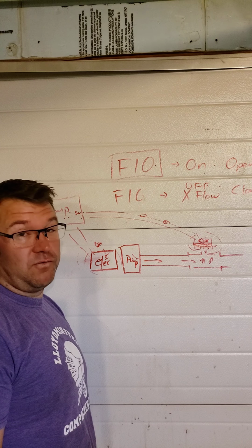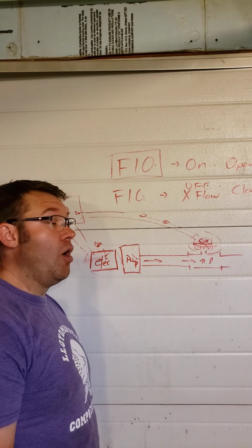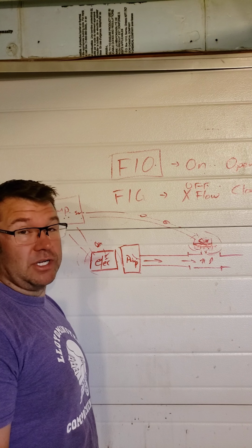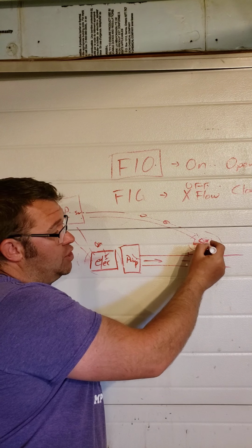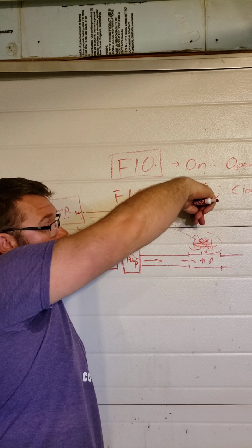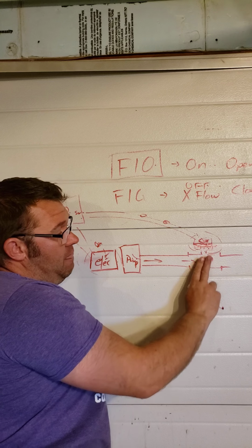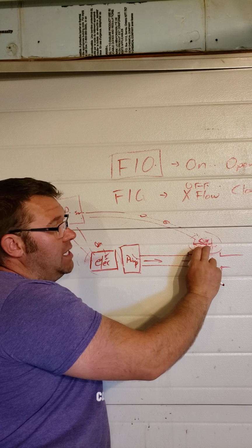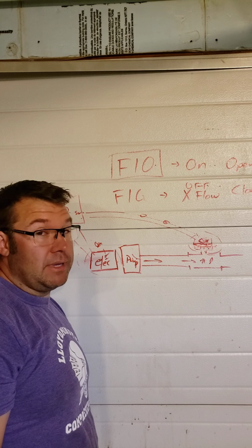Either the switch is faulty and something's broken in here and it's not making contact, or it is actually an adjustable switch. Okay, so it has an adjustment here that puts spring pressure on that diaphragm. So if it's cranked down too far, so that there'll be some sort of a threaded top on it, if there's too much spring pressure on this diaphragm, then the pump pressure can't push against that spring enough to close the switch. Now my problem is intermittent.